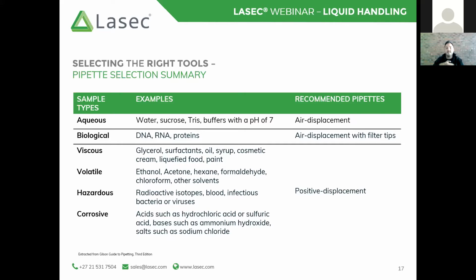So with a piston in the tip, there is a physical barrier. There is no way that any of these solutions can reach the pipette. This means that you have a relatively good safeguard that once you have discarded that tip, there will be no carryover to subsequent samples, or that your pipette itself is not contaminated.